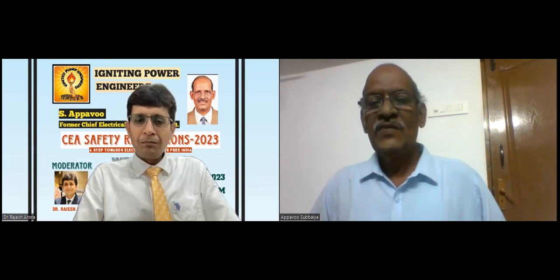Of course, a concrete encased pole is also a poor earth electrode. It can offer say 50 ohm or 100 ohm. If there are hundreds of concrete poles and hundreds of consumers, the combined earth resistance will drastically reduce. Great. And my second question is related to clause 77 of the regulation, lightning arrestor connection.